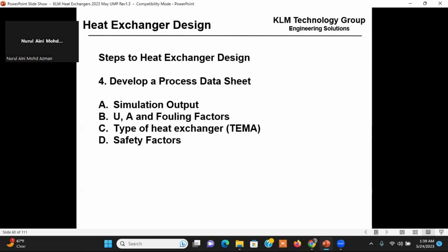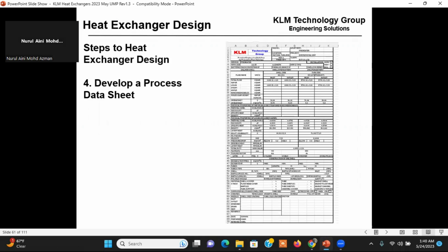All right, so we've got to develop a data sheet. So we take the simulation outputs. We've got to list the U, the A, fouling factors, the type of heat exchanger we want, and then we've got to put some safety factors in. All right, and here is that data sheet. All right, so I'm going to put my glasses on so you can see it better. Basically this is the same heat exchanger that we're talking about, and it's in Rayong, Thailand. And there's the fluid flows, there's the operating temperatures, there is the thermal conductivity, the viscosity, the specific heats, the density. All of these come straight out of the simulation.